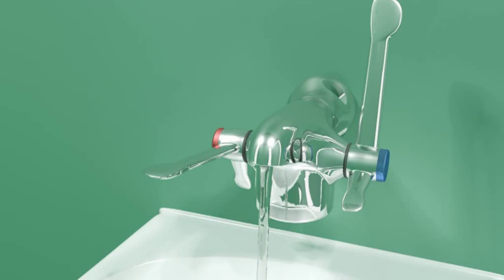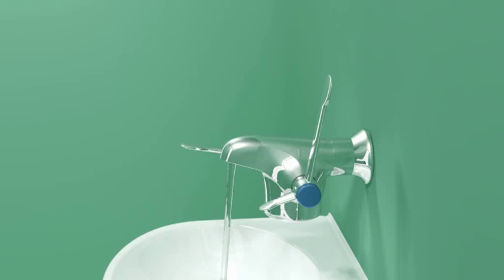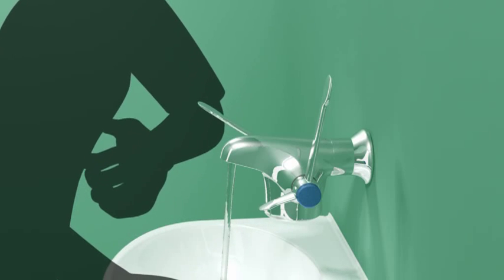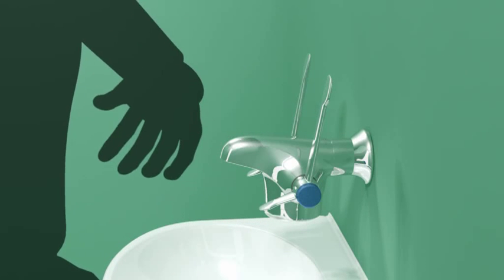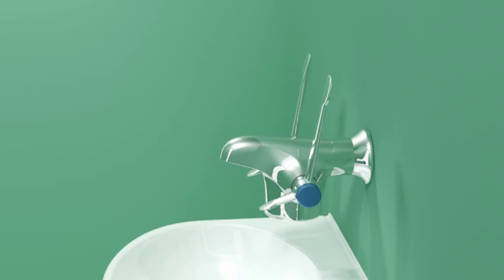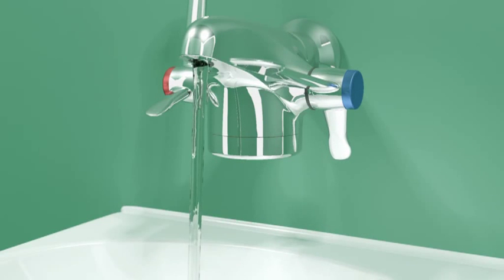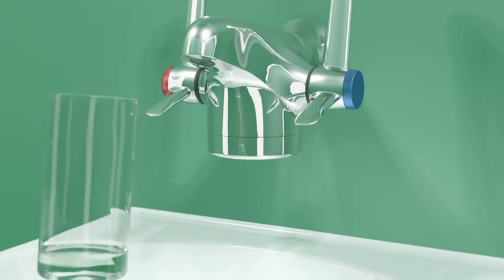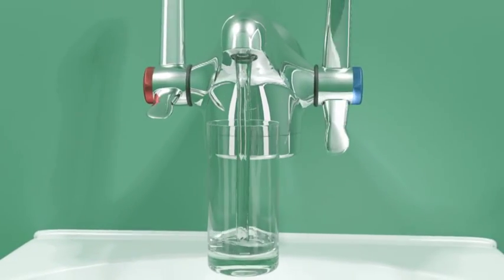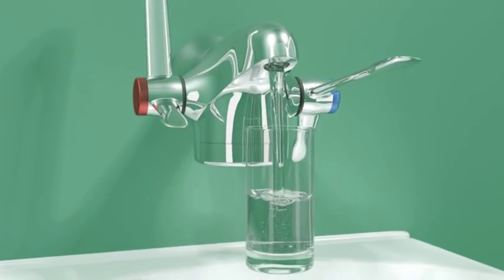To avoid recontamination of the hands after washing, turn the tap off by returning the long lever to the upright position using an elbow in a horizontal orientation. A cold water bypass of the thermostatic mechanism provides cold water for hand wash, drinking and teeth cleaning. Turn the cold lever on by pushing down on the short lever. Allow the water to run cold before filling a glass.